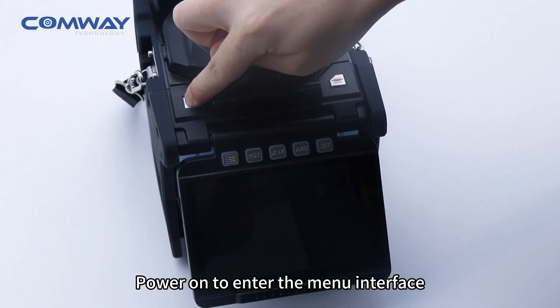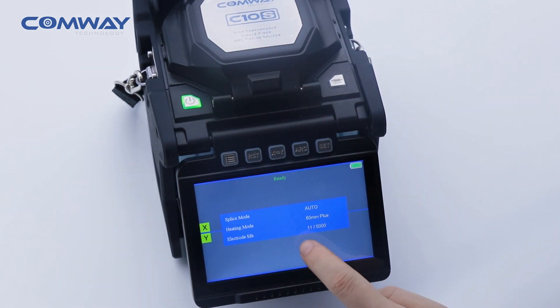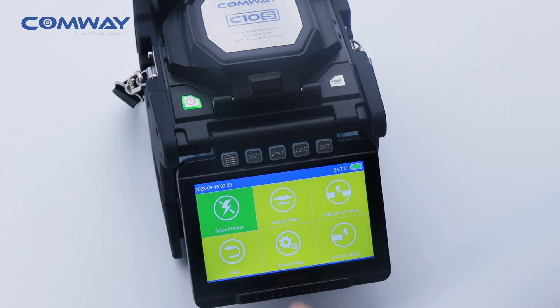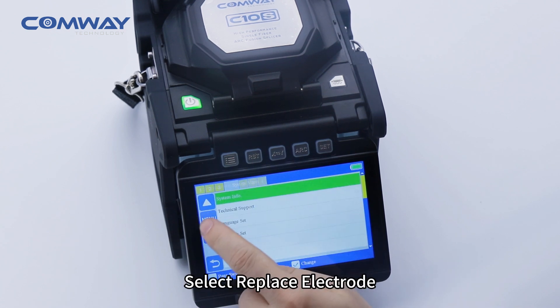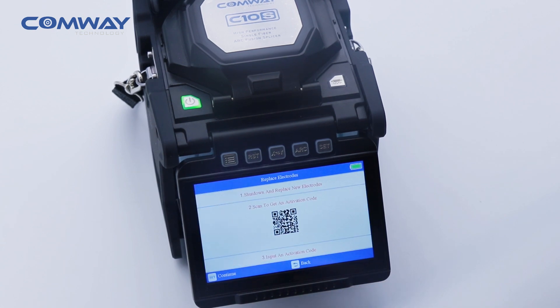Power on to enter the menu interface. Select Replace electrode. Take out the serial number card corresponding to the electrode.